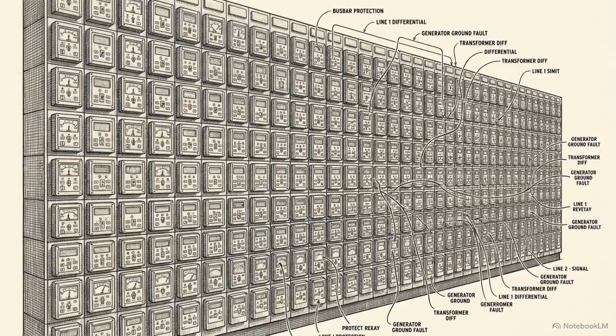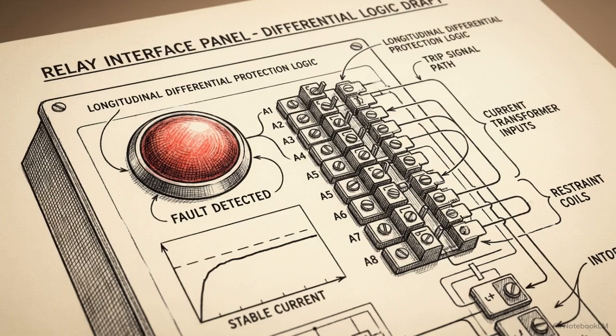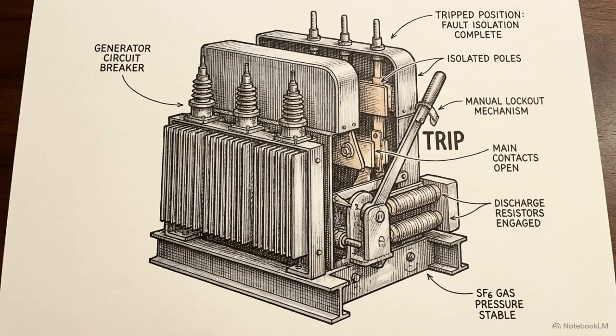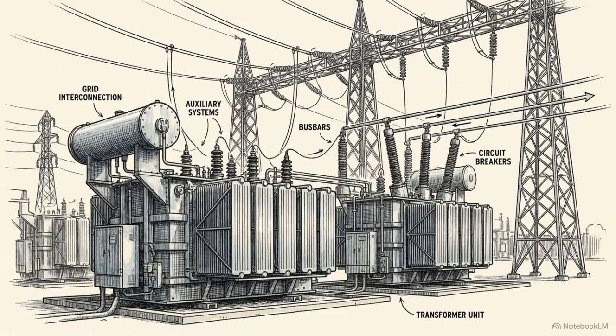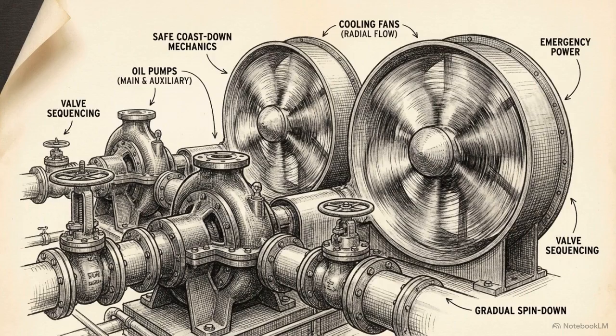Its operation is governed by an extensive relay protection matrix. This includes systems like the ANSI 87G longitudinal differential protection, monitoring internal stator faults, and the ANSI 40 relay, which watches for any loss of excitation that could throw the machine out of step. During a localized generator fault, the breaker trips to isolate the machine. However, it strategically leaves the unit auxiliary transformers connected to the 400 kilovolt grid, allowing the plant's essential cooling and oil pumps to pull backward power and coast down safely.